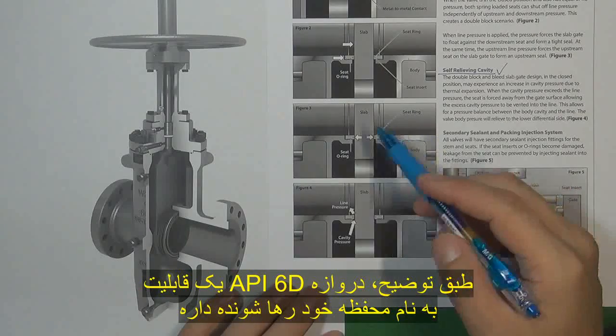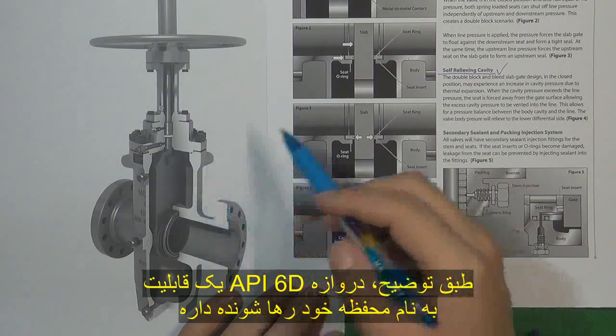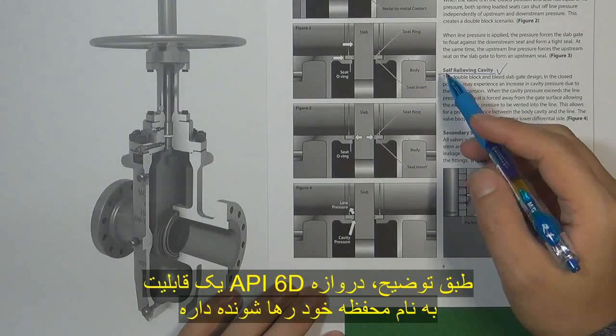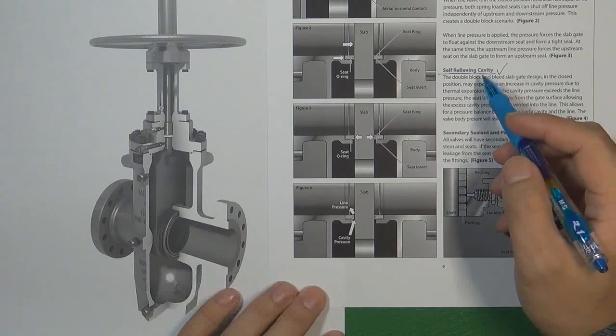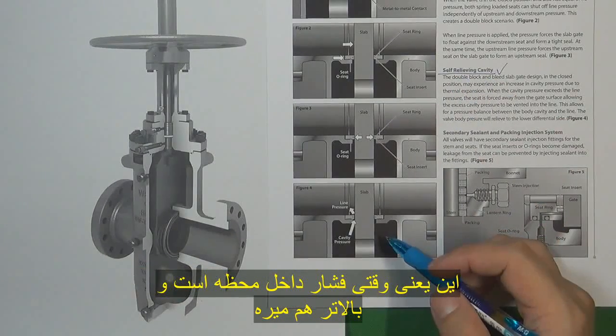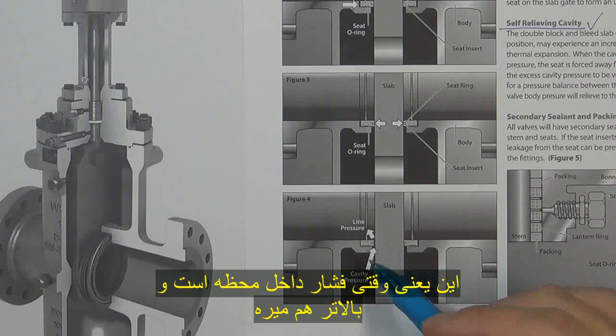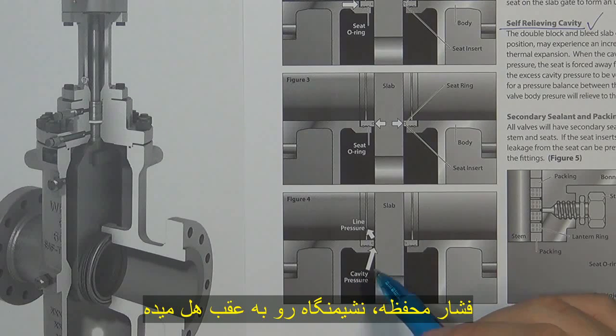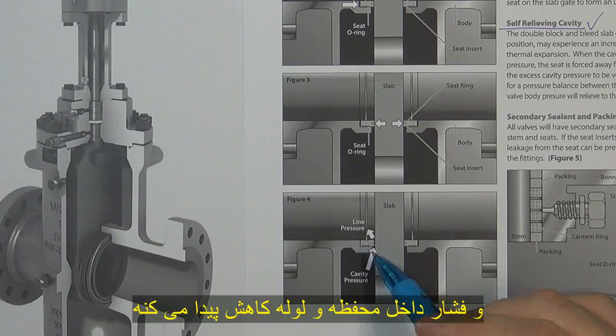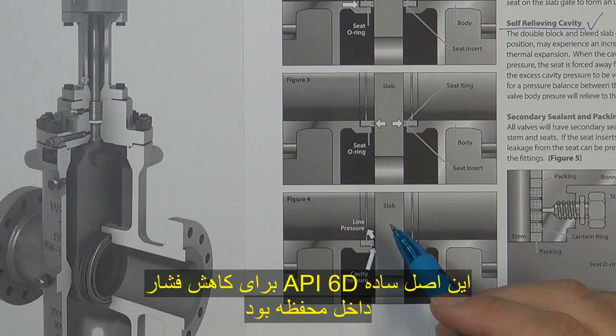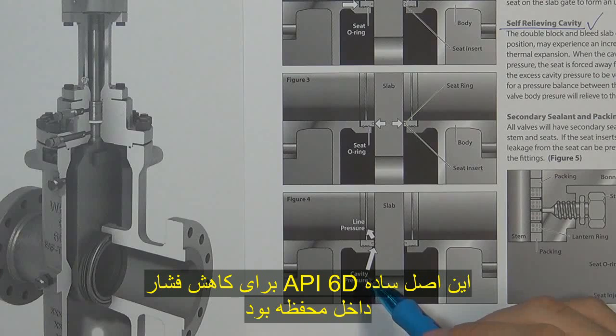According to the description, the API 6D gate valve has one kind of function called a self-relieving cavity. That means when the cavity has pressure inside and the pressure goes higher, the cavity pressure can push the flexible valve seat back and relieve the pressure inside the cavity to the pipe. So that is the basic principle for the API 6D gate valve to relieve the pressure inside the cavity.